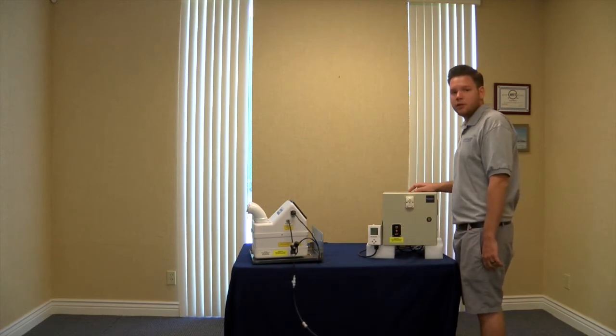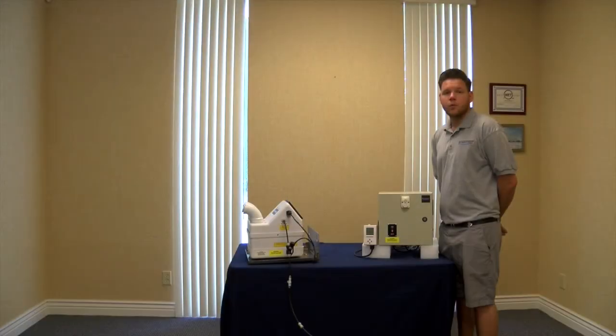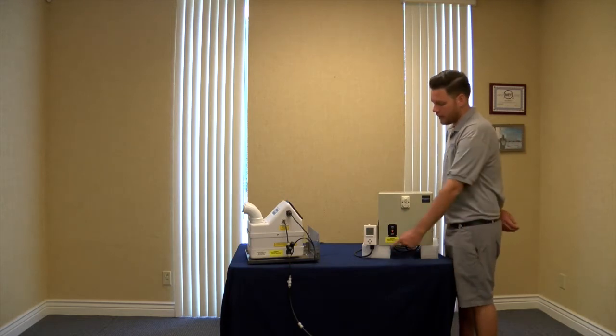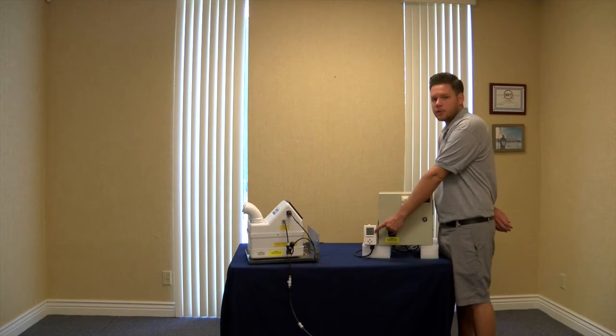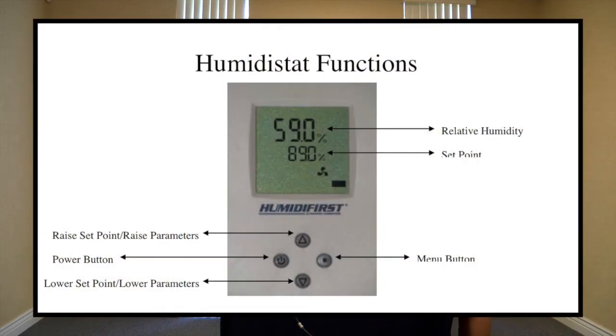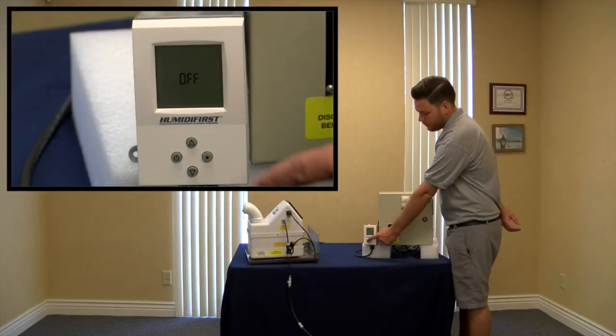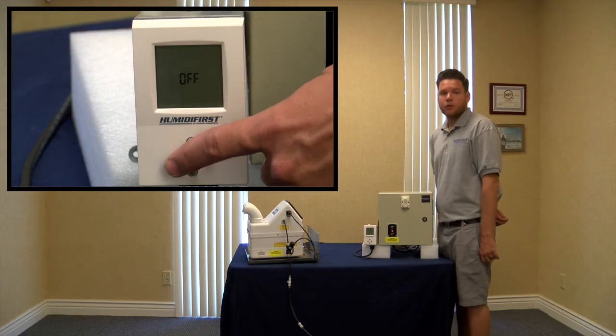Once you turn on the unit mount control panel, you will hear the 24-volt VAC solenoid engage. Once the desired water level is met inside of your MistPack humidifier, the 24-volt solenoid will disengage. You will notice that your humidistat is in the off position. To turn it on, simply locate the power button on the left-hand side of the controller and press it. Once pressed, it will give you a digital readout.